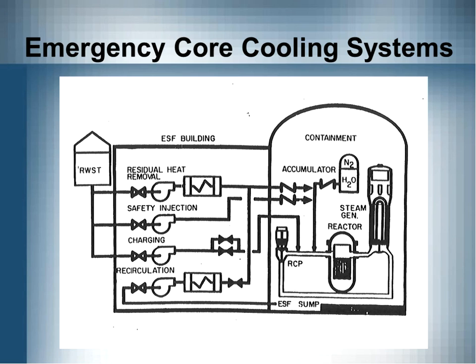And the other system we've got is our recirculation system. You see that this actually takes suction off the bottom of the containment itself. The purpose of this is, once we have our leak, the water comes out, and we're doing nothing but pumping water in. It's being fed up by the core, drains back out, goes into the sump, and we can take it out with the recirculation pump, pull it off, and then pump it back in. So this is the feature we would use basically to cool down the core if we had an accident. We just take it out of the sump, put it through the cooler, and back into the core.